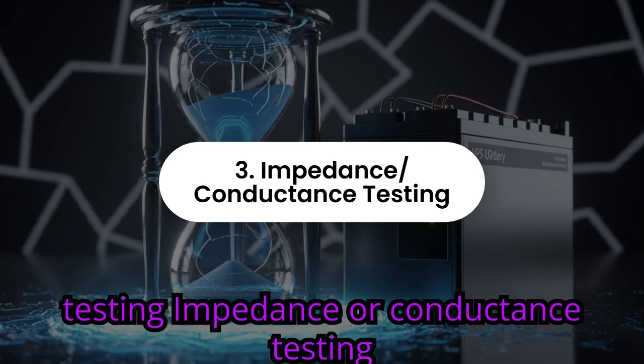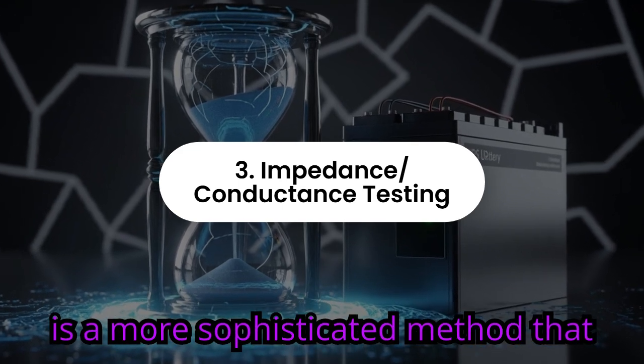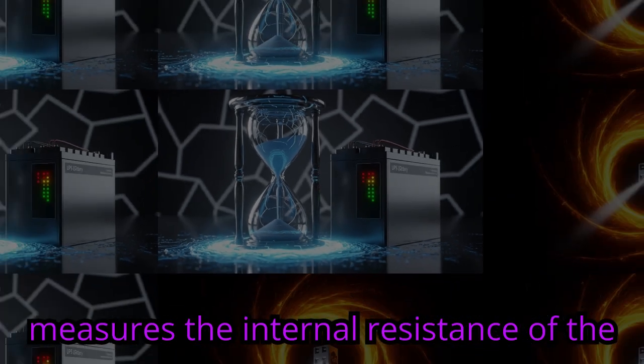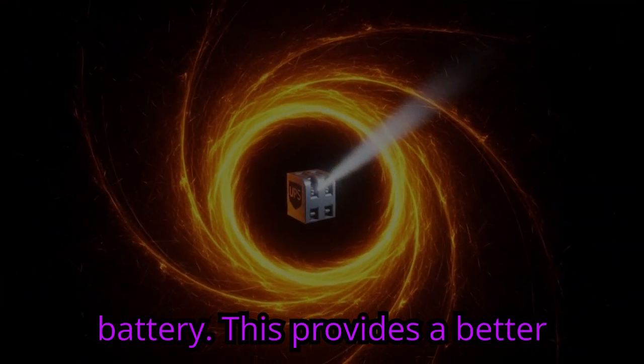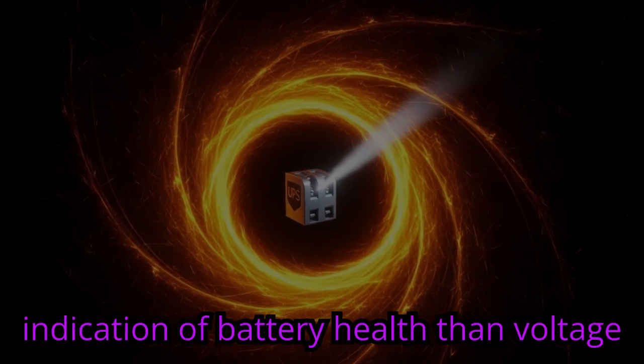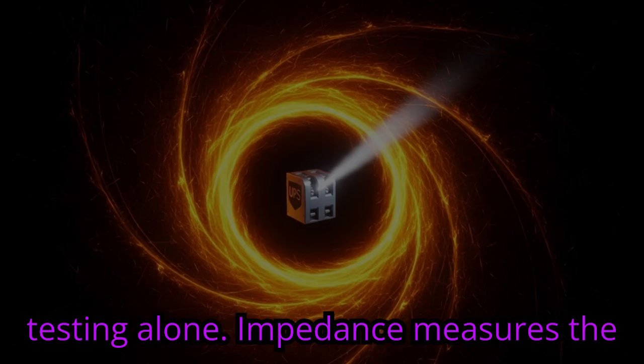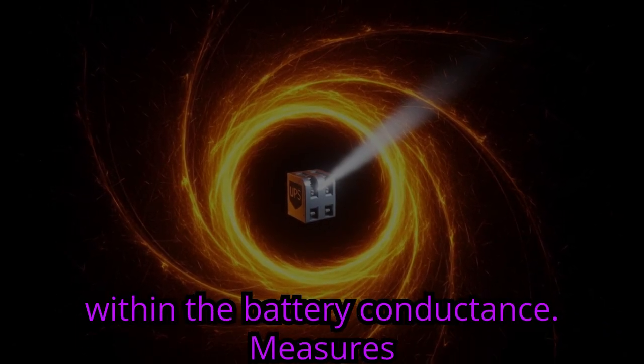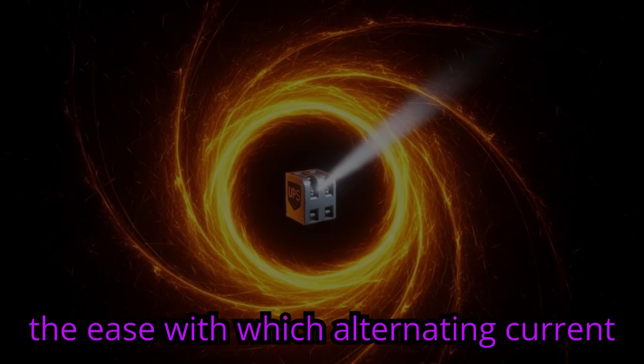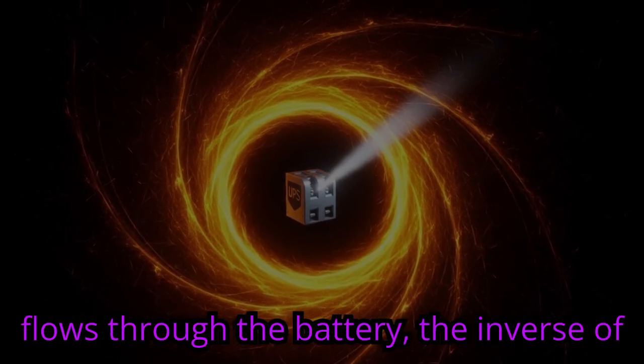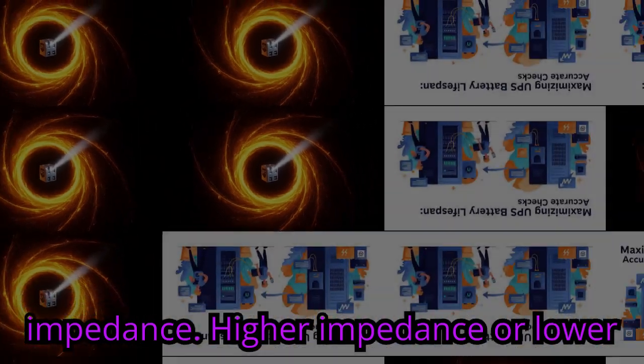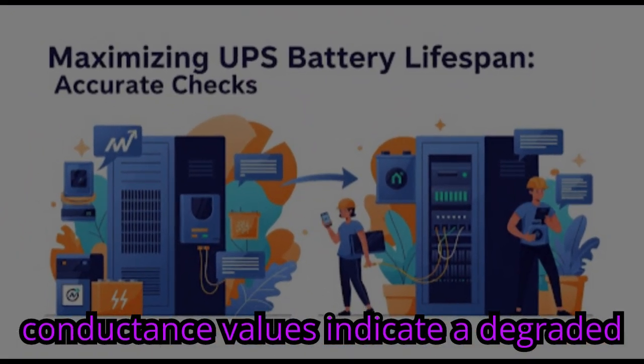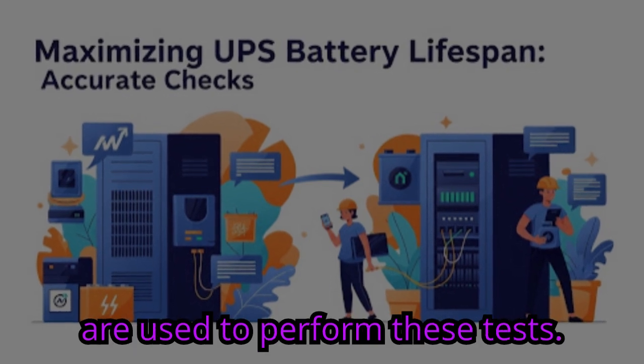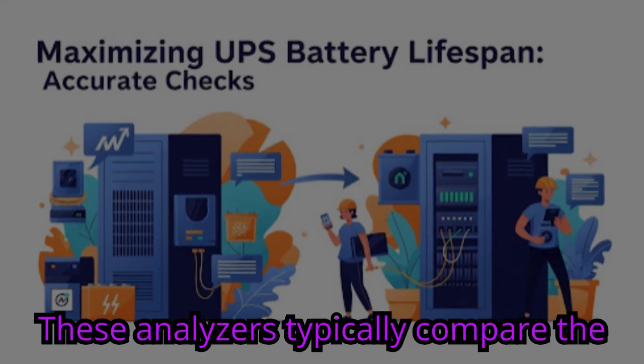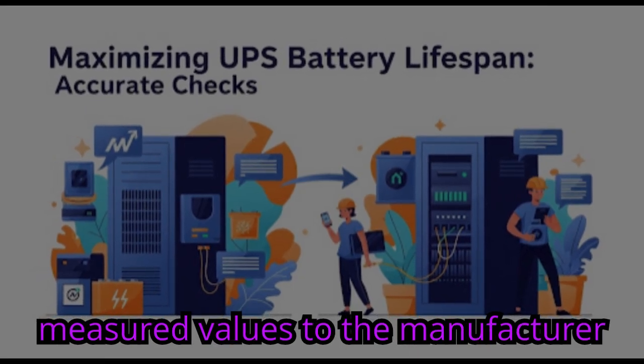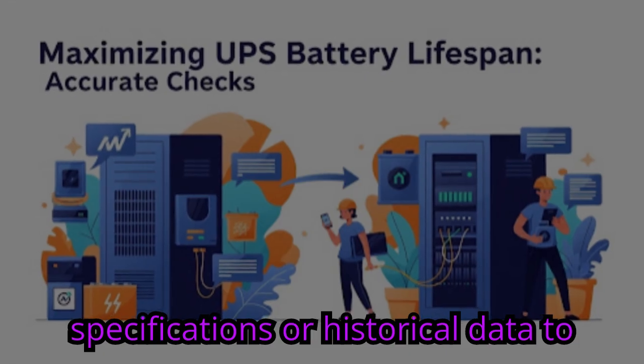3. Impedance conductance testing. Impedance or conductance testing is a more sophisticated method that measures the internal resistance of the battery. This provides a better indication of battery health than voltage testing alone. Impedance measures the opposition to alternating current flow within the battery. Conductance measures the ease with which alternating current flows through the battery, the inverse of impedance. Higher impedance or lower conductance values indicate a degraded battery. Specialized battery analyzers are used to perform these tests. These analyzers typically compare the measured values to the manufacturer's specifications or historical data to determine battery health.